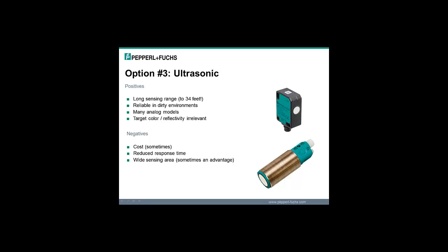So if inductives and optic sensors don't do the job, the next solution is going to be an ultrasonic sensor. And some of the positives about an ultrasonic sensor are the long sensing range. We have some models that go out to 34 feet, which is 10 meters. They're very reliable in dirty environments because it's sound, it's not optical. So there's no problem with dirt on the face. The sensors work great. There are many analog models, so if you need a continuous feedback of how close or far away something is, not just if it's on or off, there's a lot of options with ultrasonics. And target color and target reflectivity, like optical reflectivity, is irrelevant. Sensors work great whether the target's black or white or pink.